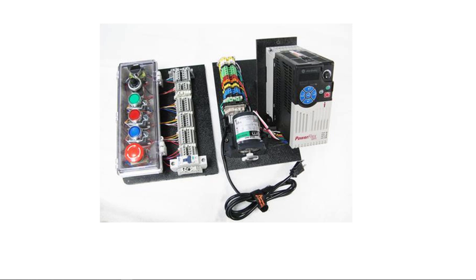Then they have a circuit that takes that energy and converts it to three-phase AC at a frequency that you determine by the speed that you select for this drive. Because AC motors, the speed is determined by the frequency. So we have the VFD there and then we have a small three-phase motor. That's a 230 volt three-phase motor.